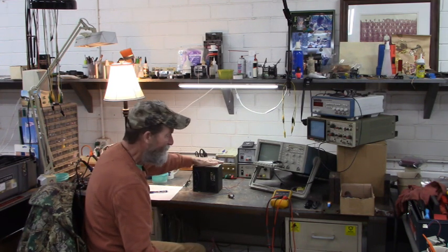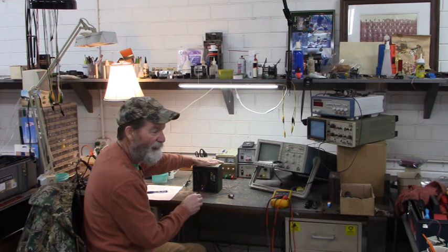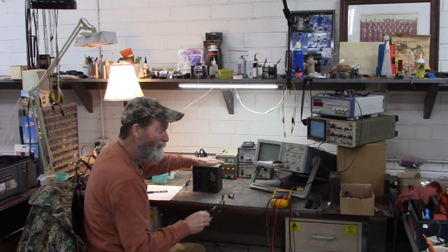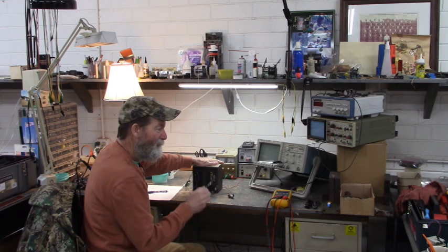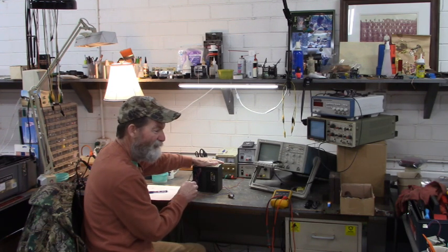So you have to go inside here, unsolder those five contactors, take them apart, clean the contacts, put them back together, resolder them to the board.